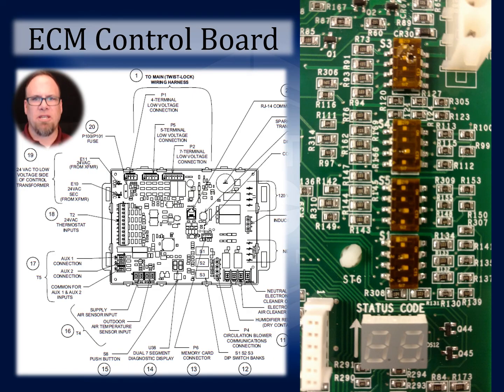Okay, this one's a little bit different because here we actually have a control board for a more advanced system that has an ECM motor or a variable speed motor. And you can see on the left-hand diagram out of the manufacturer's installation instructions, there's some switch banks there. And ironically, the way that those are labeled is S1, S2, S3, those are switch banks. And they don't necessarily always work out that way.